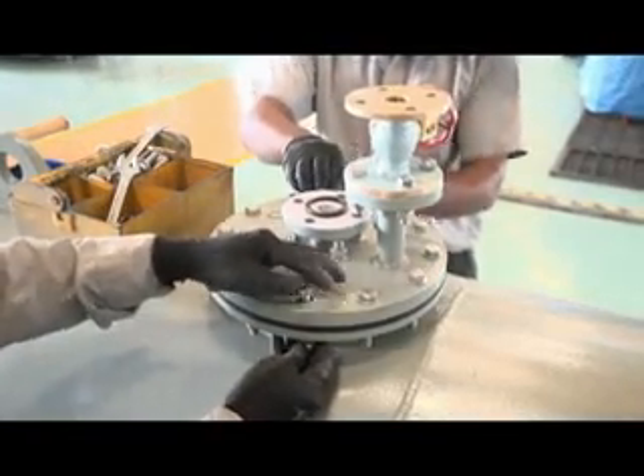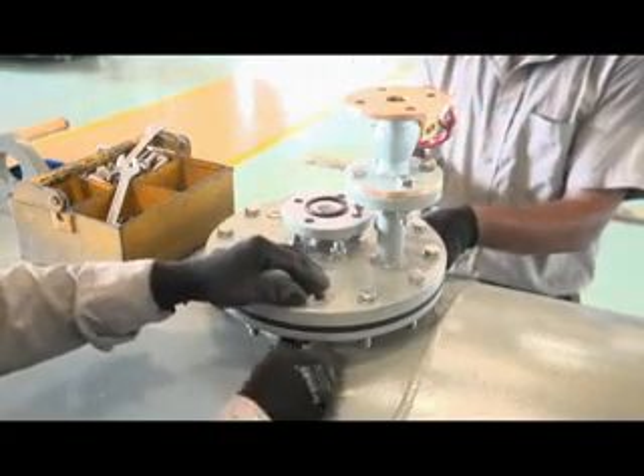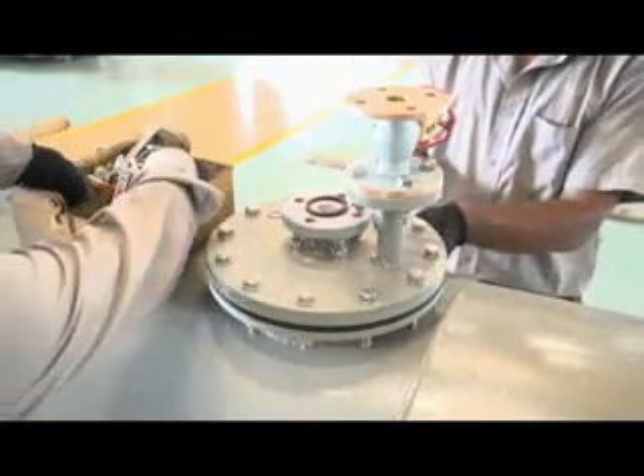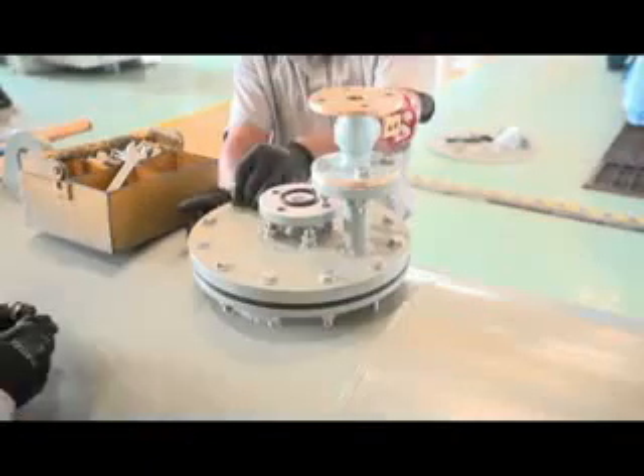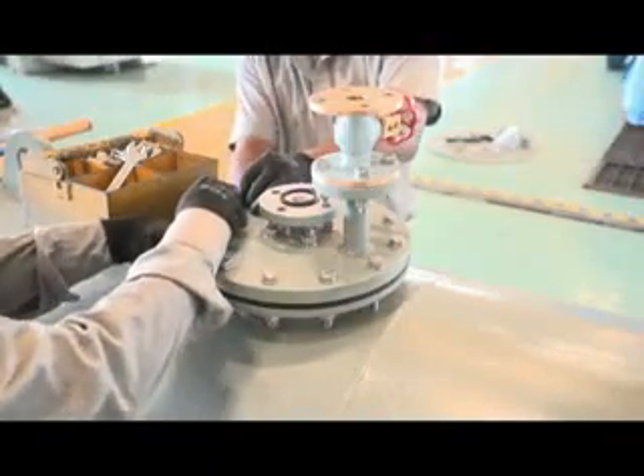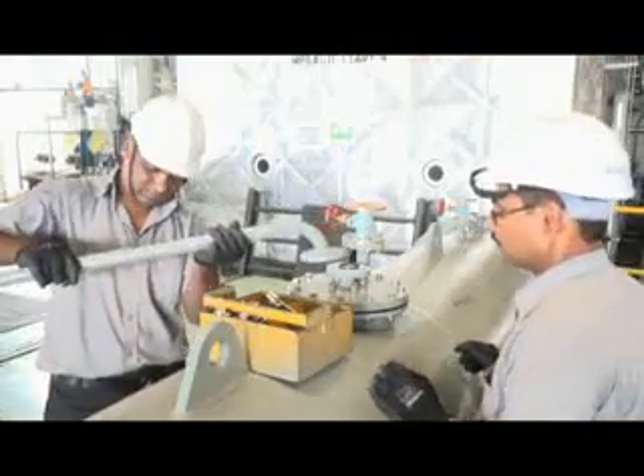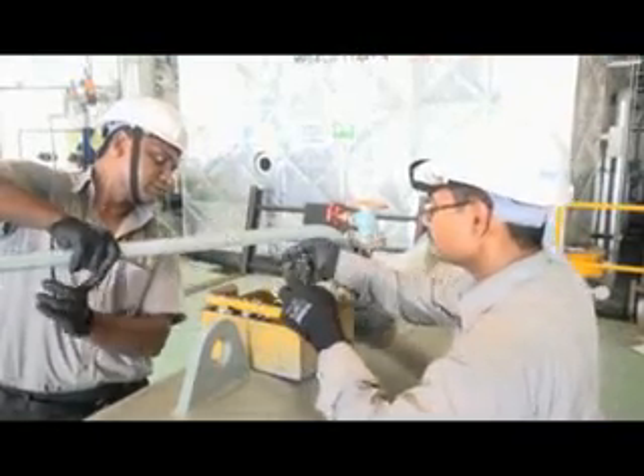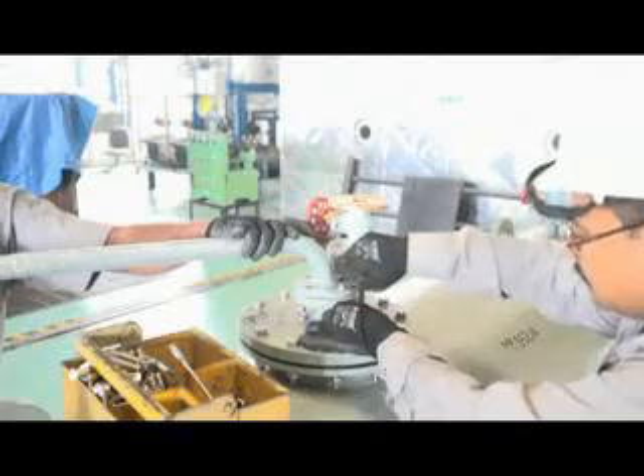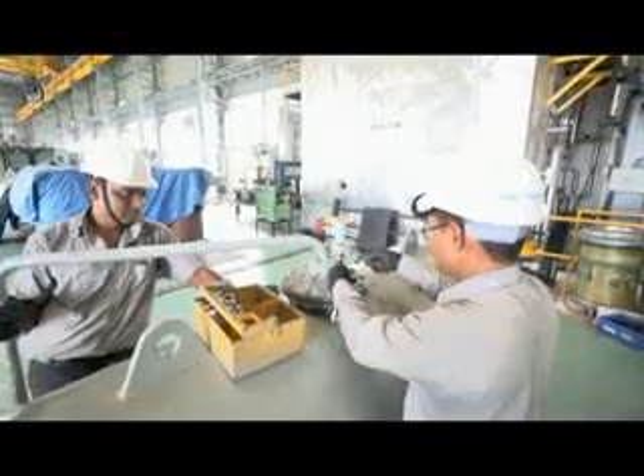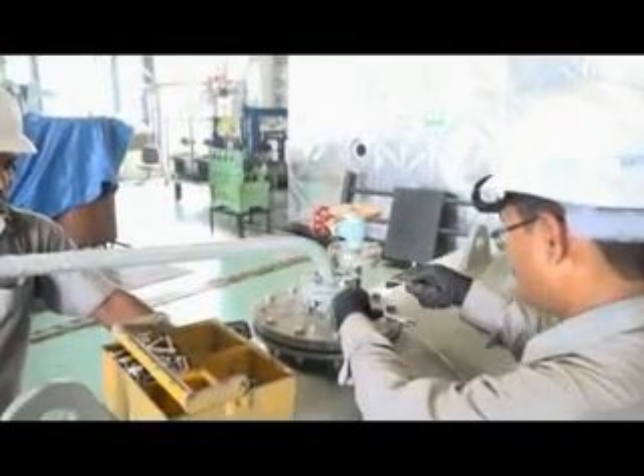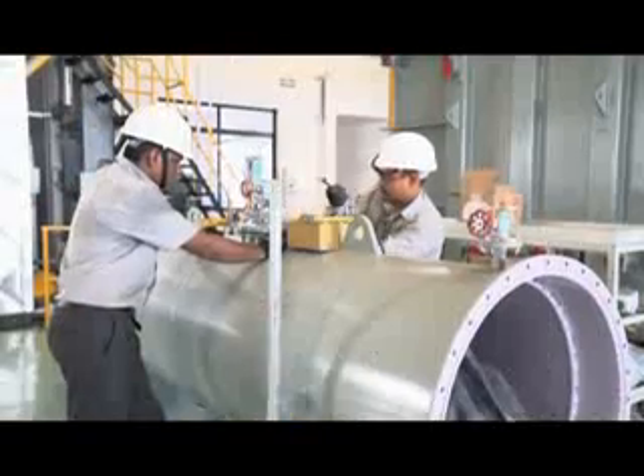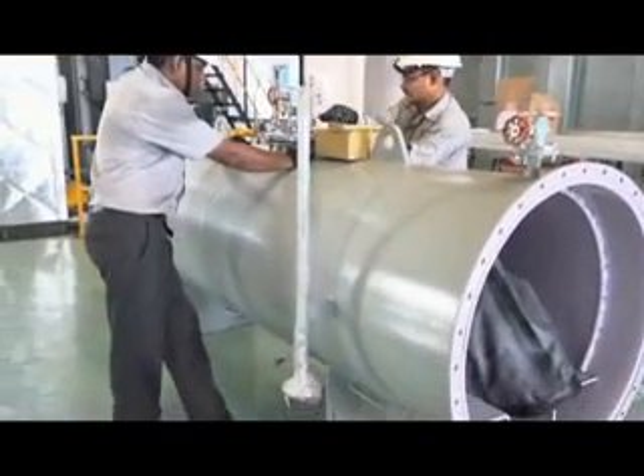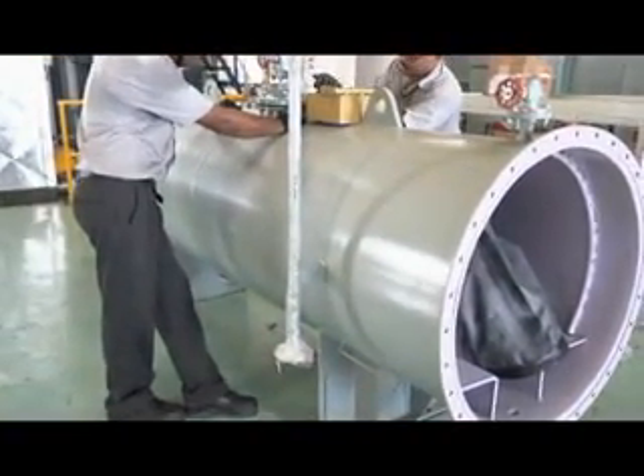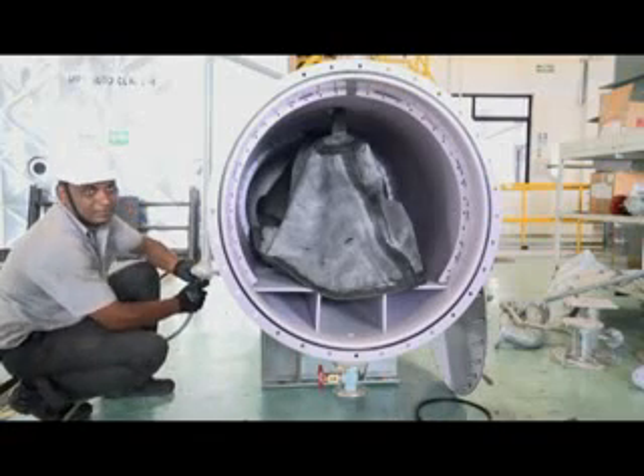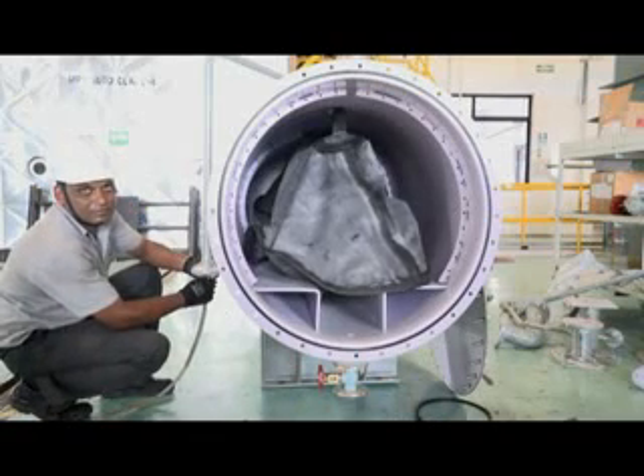Simple design with no expendable parts, needs negligible man-hours for inspection. Extended service life. Economical. Prevents corrosion. Oil can be filled into the transformer tank without being exposed to the air. Since insulating oil is completely isolated from the atmosphere by an air cell, there is no possibility of oxygen or moisture penetrating the oil. Pressure on the surface of the oil is constantly maintained at atmospheric pressure, offering no possibility of the oil becoming supersaturated and forming bubbles. Thus, high dielectric strength can be maintained.